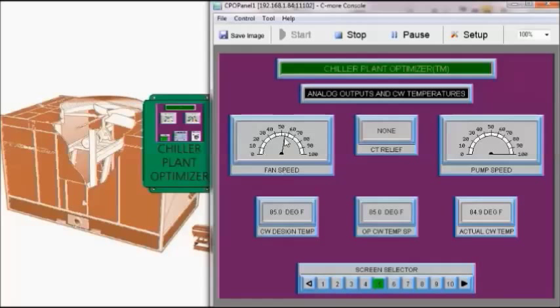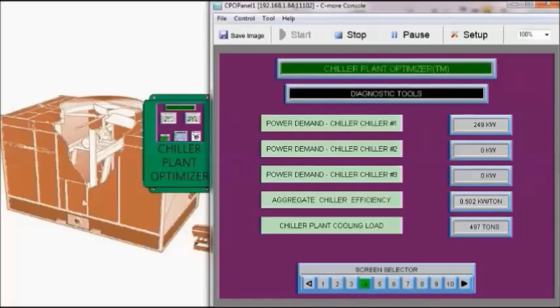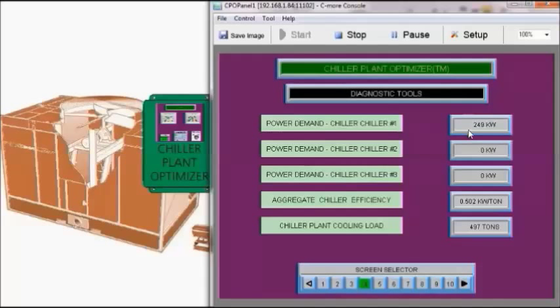The biggest change is the cooling tower fan speed. It has dropped to about 55-56% and we're still operating at an actual condenser water temperature of 85 or 84.9 degrees Fahrenheit. So our power demand has dropped to 249 kilowatts. We're operating at a chiller efficiency of 0.502 kW per ton and our chiller load has dropped to 497 tons.